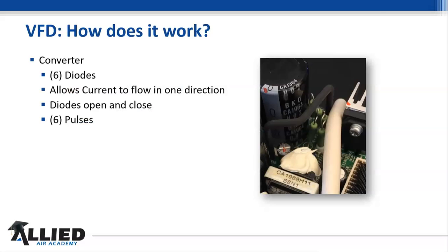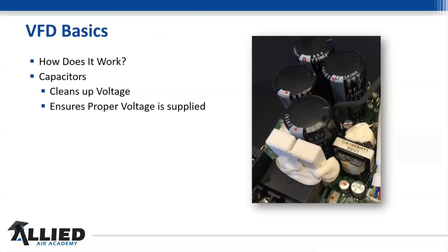Now, you've got 6 diodes, and this is just our particular ones, okay? So there's 6 diodes in there, and diodes are like check valves for voltages. So it allows current to only flow in one direction, diodes open and close, and you get pulses. I'm going to show you a chart in just a minute that kind of shows you that, but that's why this voltage has to be good and clean going into these units that have this. And capacitors. All right, so DC voltage is not the cleanest voltage in the world sometimes, so it needs to be cleaned up, and that's what the capacitors do.